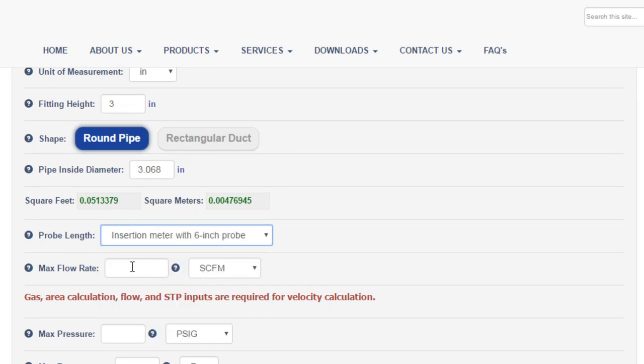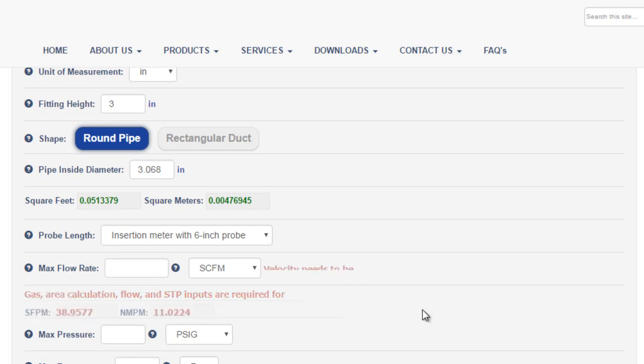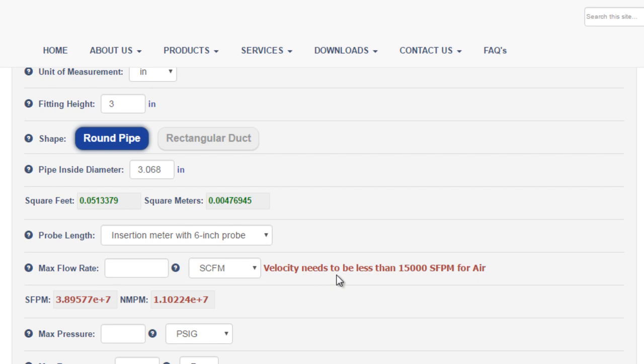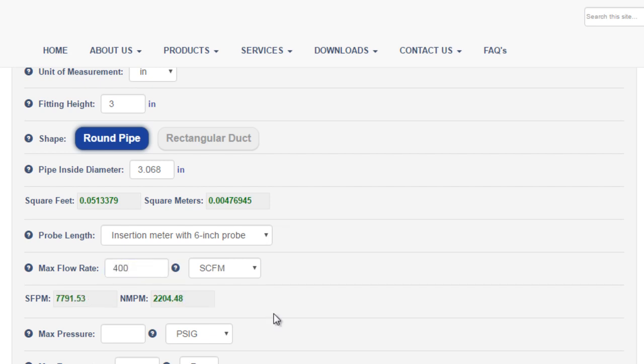Next we'll enter in our maximum flow rate. Note that there are limits to this value. If my flow rate is too low, I'll receive an error message. If my flow rate is too high, I'll receive a different error message. The Configurator is checking to make sure that my application is within spec of the meter. Once we enter a flow rate value that is within spec, the error message will go away and we'll be given a velocity calculation for that flow rate in that pipe size. The velocities are listed in standard feet per minute and normal meters per minute.